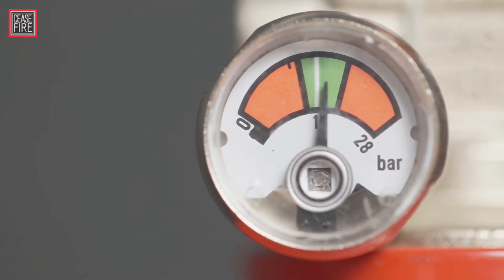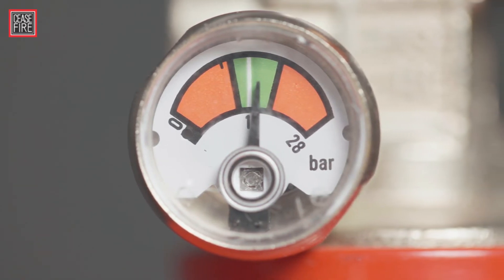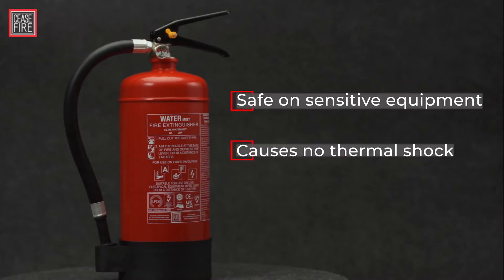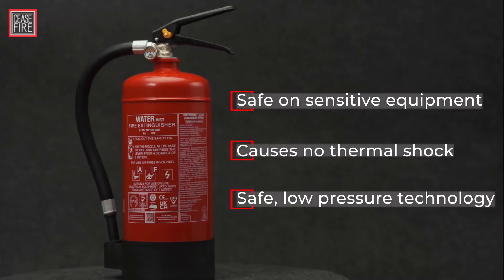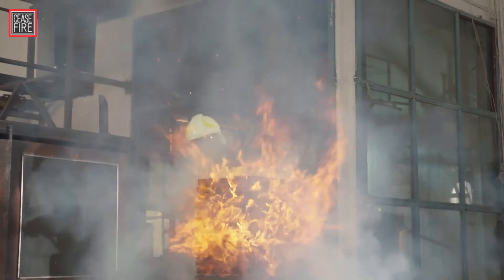Being a low pressure extinguisher pressurized only at 15 bar, as compared to a high 70 bar pressure in CO2, water mist extinguishers are absolutely safe for the user and occupants of the premises. Water mist extinguishers do not pose a single operational challenge.